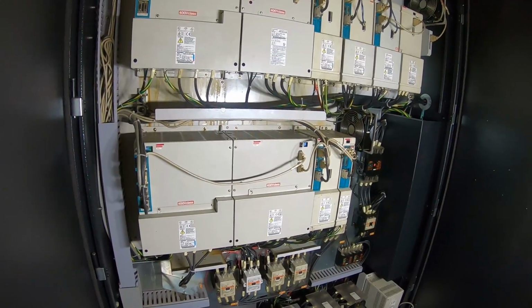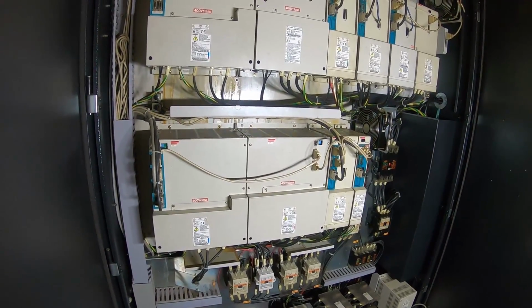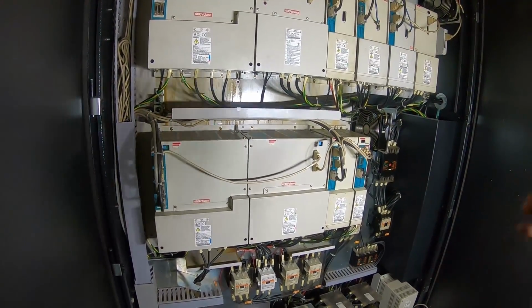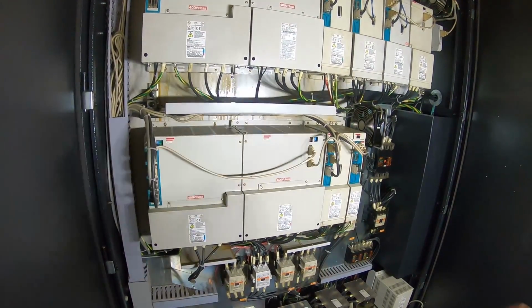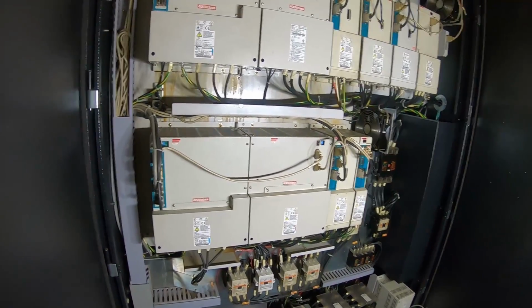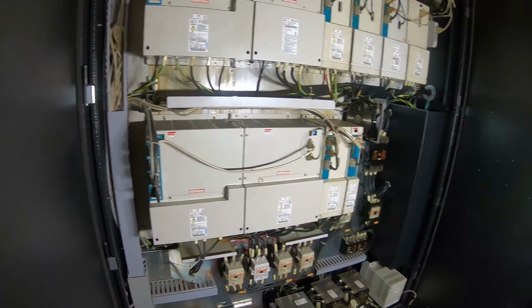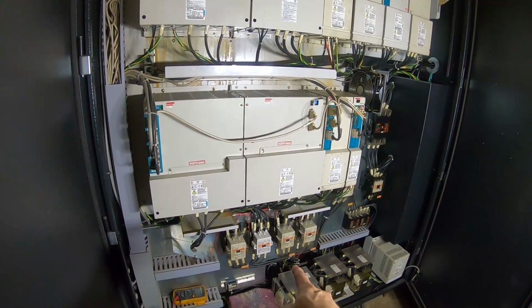So I kind of learned my lesson on this one. I should actually turn that main circuit breaker off when I turn the control off. I hadn't been doing that, and that's what caused this relay to go bad.